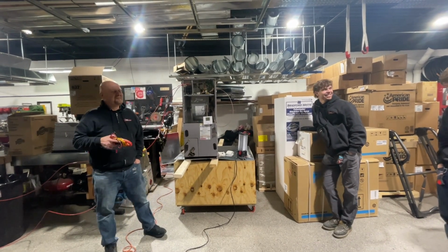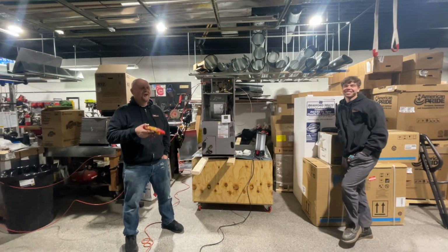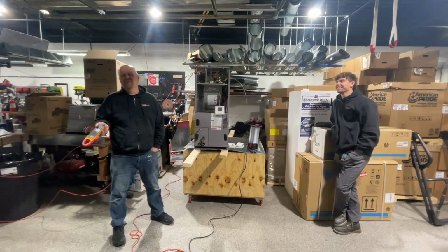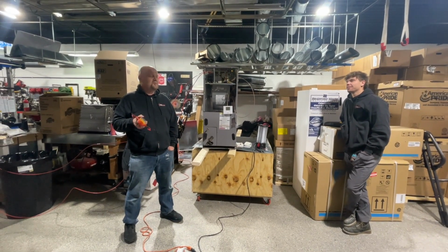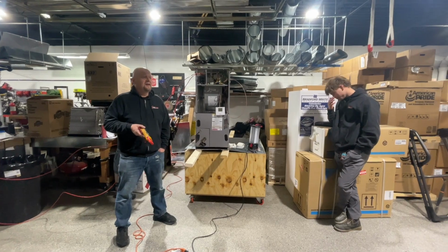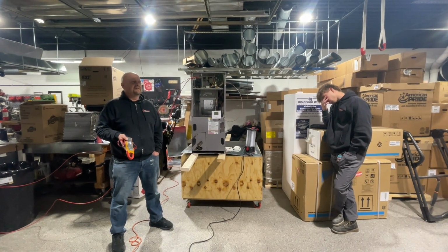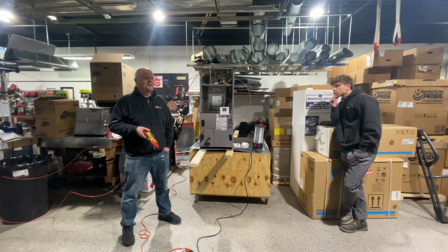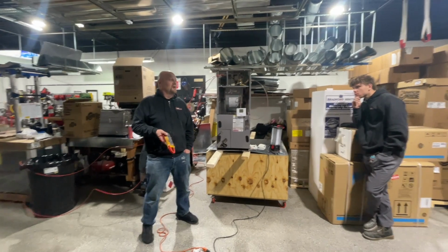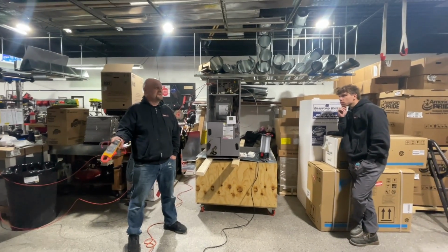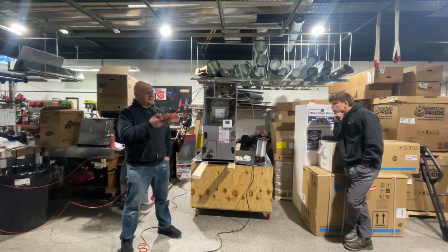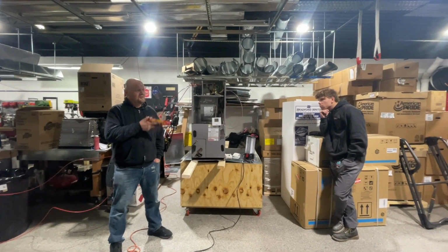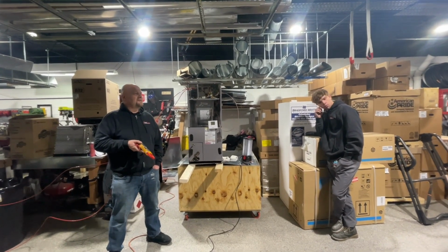If it's an older house, yeah, 40. If it's a super tight house, it's actually 20. A newer house built after 1990 is supposed to be 30. But if you go 40, you're never going to be wrong, just because sometimes it gets colder. So having said that, this being 32,000 BTUs, go 32,000 and divide it by 40.